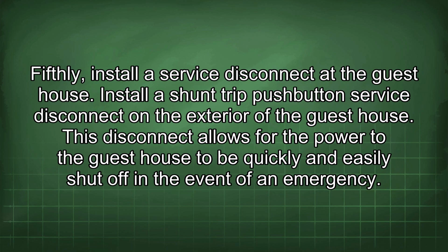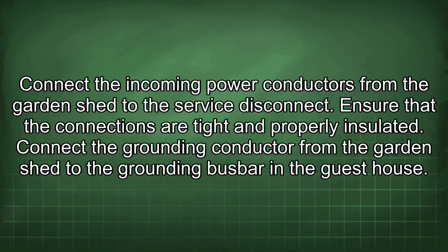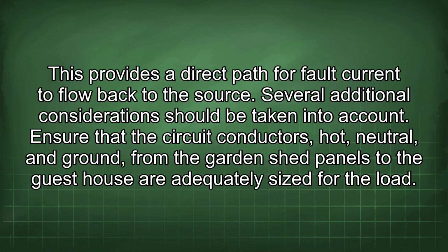Fifthly, install a service disconnect at the guest house. Install a shunt trip push-button service disconnect on the exterior of the guest house. This disconnect allows for the power to the guest house to be quickly and easily shut off in the event of an emergency. Connect the incoming power conductors from the garden shed to the service disconnect. Ensure that the connections are tight and properly insulated. Connect the grounding conductor from the garden shed to the grounding busbar in the guest house. This provides a direct path for fault current to flow back to the source.